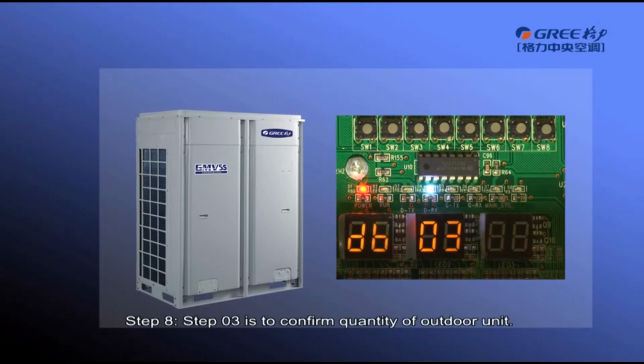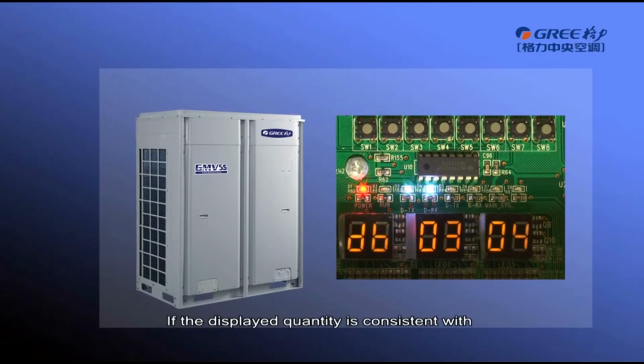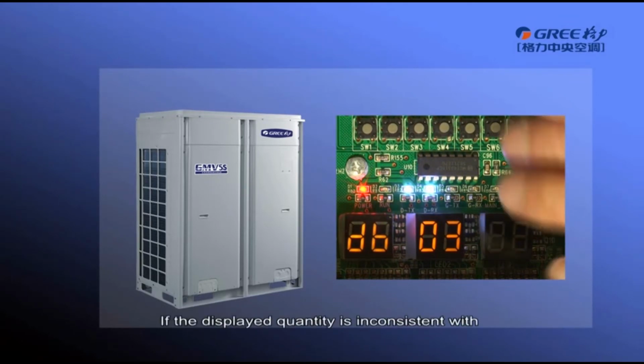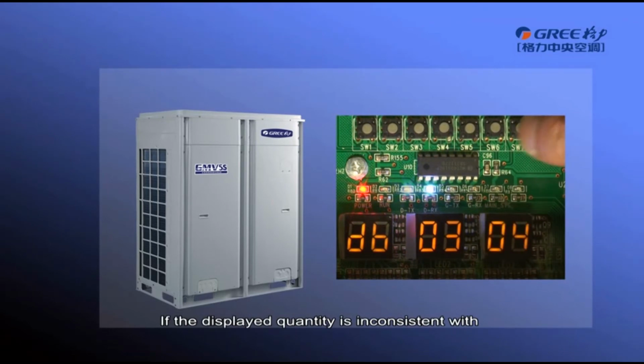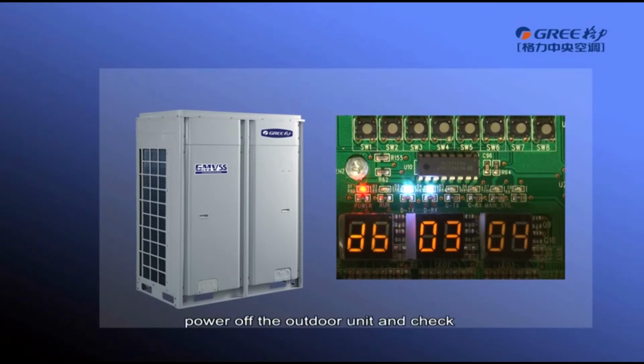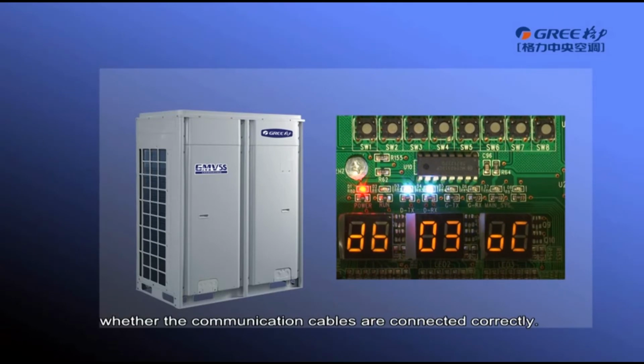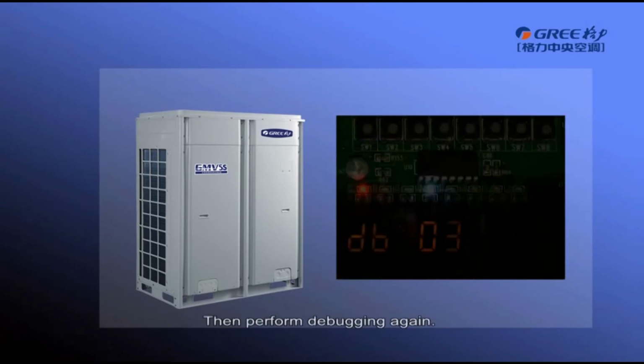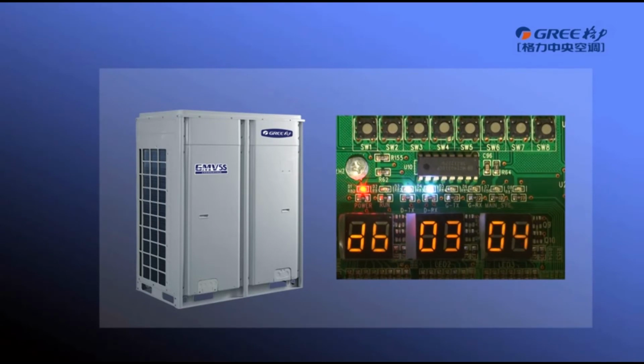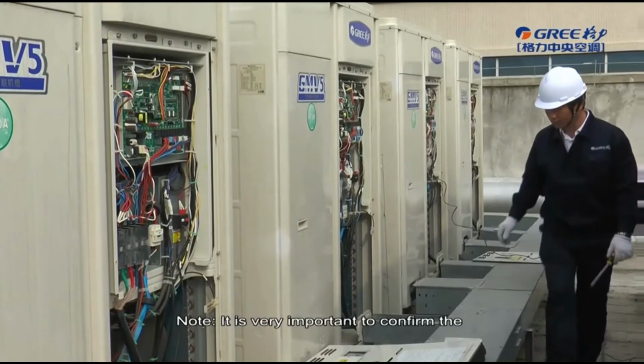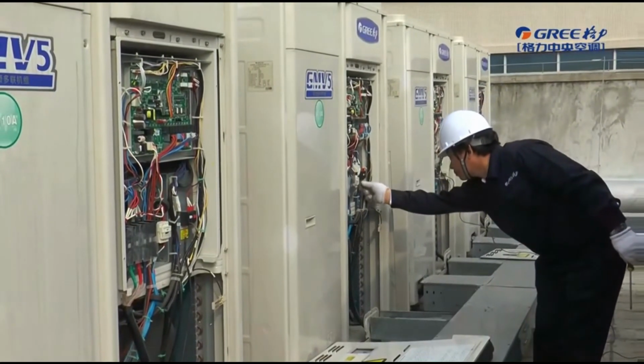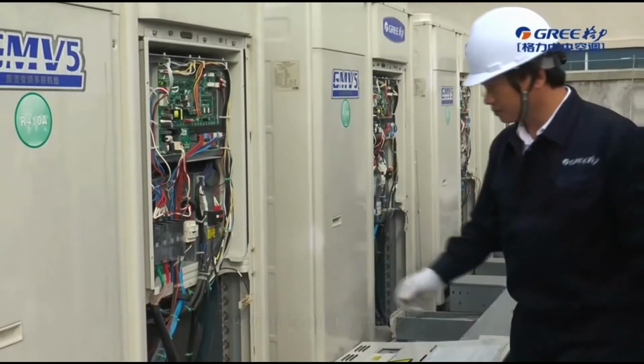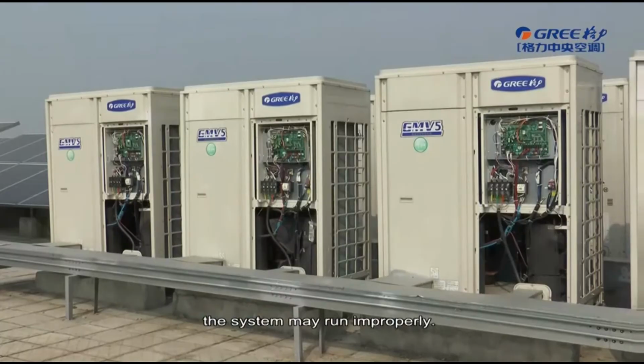Step 3 is to confirm quantity of outdoor unit. If the display quantity is consistent with the actual connected units, the unit enters step 4 automatically. If the displayed quantity is inconsistent with the actual connected units, power off the outdoor unit and check whether the communication cables are connected correctly. Then perform debugging again. It is very important to confirm the quantity of the outdoor units. If the confirmed quantity is inconsistent with the actual quantity, the system may run improperly.